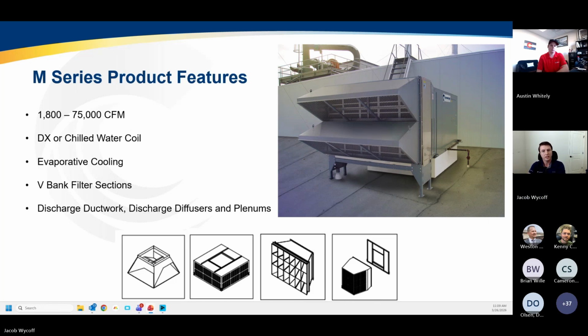So these are generally minimally ducted units, meaning you're providing a very small amount of ductwork just to get the air into the space, and then you're throwing that air across the facility. And then wherever the exhaust is located is going to pull that air towards the exhaust. As such, typically there's not a whole lot of ductwork required, and we'll provide that minimal ductwork as well as the discharge diffusers and plenums to allow the unit to show up as a single package for quick, easy installation that the project manager on the project doesn't have to worry about.